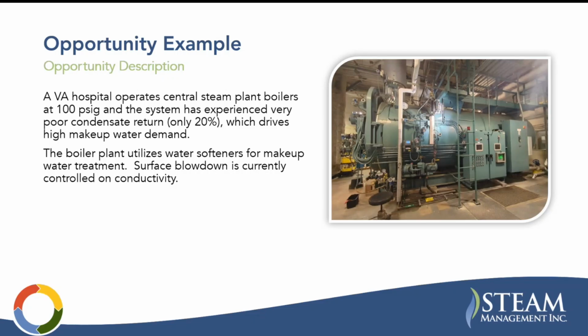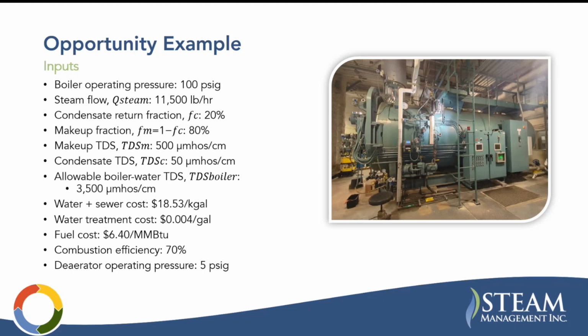So this particular plant has a deteriorated condensate return system. They have given up on returning condensate from a lot of the users in the facility, and they're basically dumping condensate to ground. So they have only about 20% condensate return. Some inputs here: operating pressure 100 pounds, steam flow 11,500 pounds per hour. So that's something to note. This is a pretty modest steam flow. But again, condensate return only 20%.